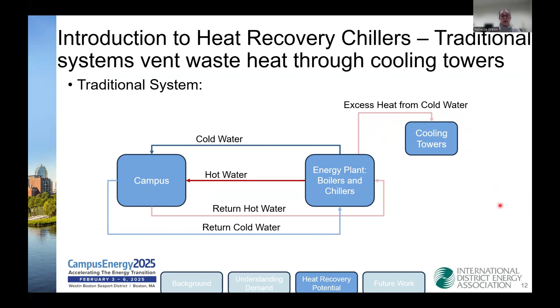So again, you have your energy plant with boilers and chillers, you have campus, and then we add a little box here, which represents the heat recovery chiller. What happens is your return hot water and your return cold water go to a heat recovery chiller. Inside the heat recovery chiller, the cold water, which is not as cold as it should be because the cooling has been used, and the return hot water, which is colder than it should be because the heating has been used, get sent into the heat recovery chiller. Basically the heat is extracted from the cold stream and put into the hot stream with a little bit of input from electricity as well as the heat recovery chiller.